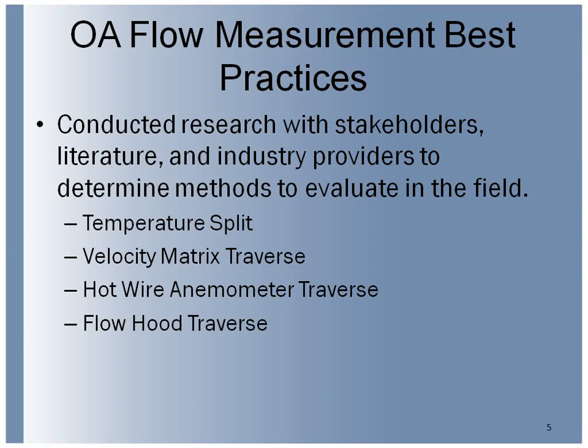We looked at a few different methodologies, more than this actually, but the dreaded temperature split, velocity matrix traverse, which is basically a 1x1 square field of pitot tubes giving an average velocity flow over a 1x1 square, hot wire anemometer, and the flow hood.